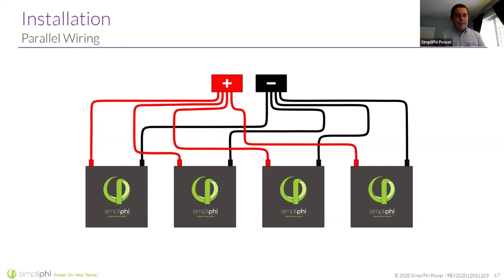This is an example of parallel wiring. The other thing you'll notice is that this black wire takes some roundabout ways to get there. That's because all these battery cables are the same length, which keeps resistance to the batteries equal. If you have different battery cable lengths, the batteries will see different resistance and discharge unevenly. So it's important to always parallel, and for our 5 batteries, always keep similar battery cable lengths.